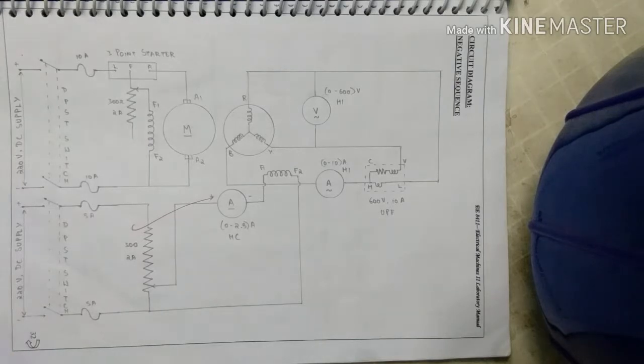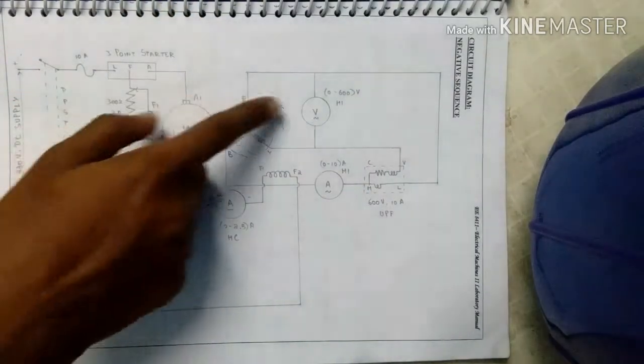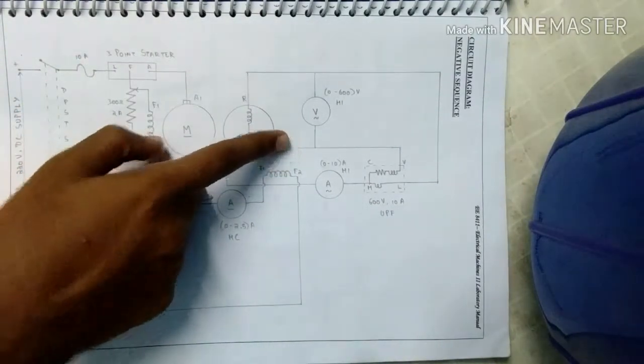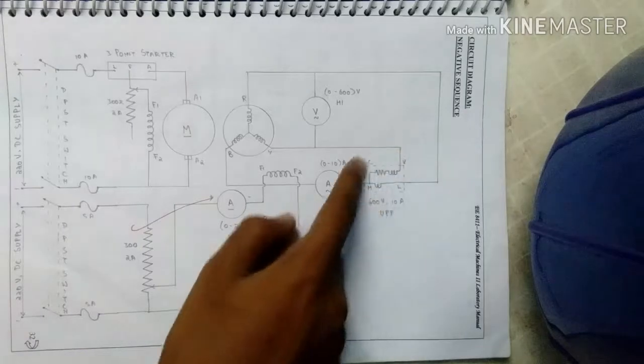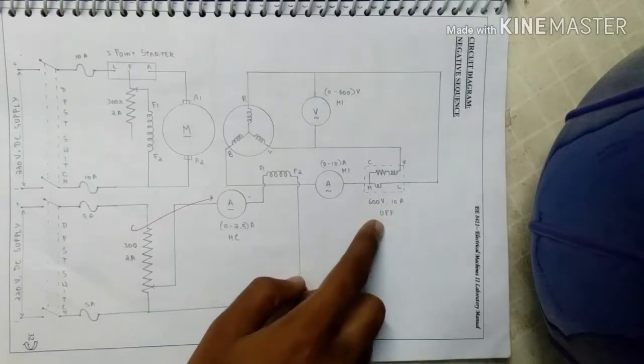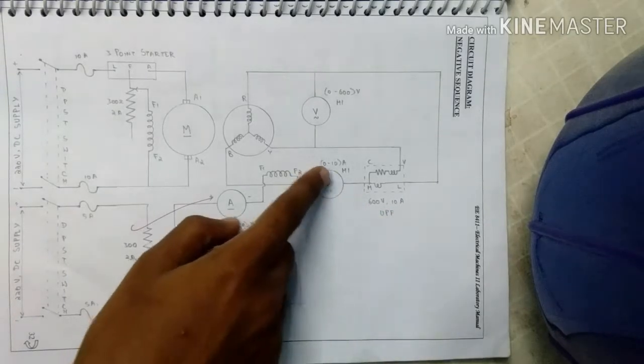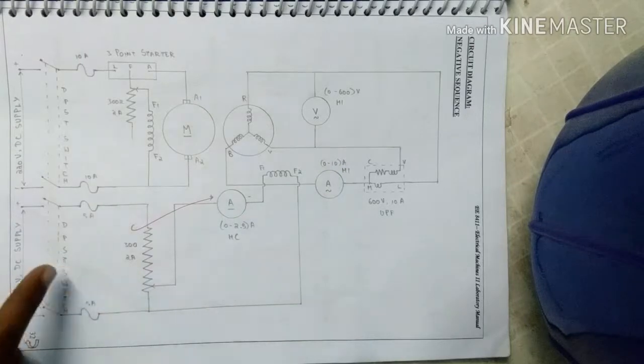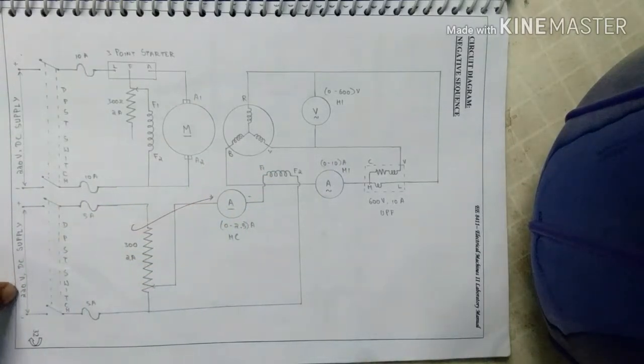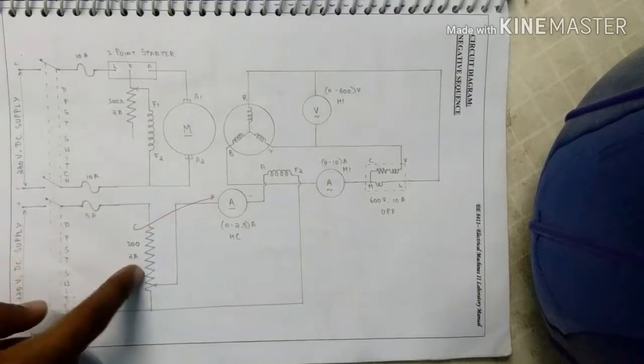For negative sequence, this is a circuit diagram. Here we connect the voltmeter across any two phases and then we connect here a wattmeter that is 600 volt 10 ampere UPF. And then here we connect an ammeter 0 to 10 ampere. The field winding is excited by a separate 220 volt DC supply. Here we connect a rheostat.